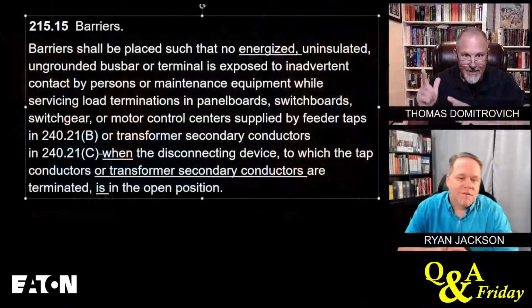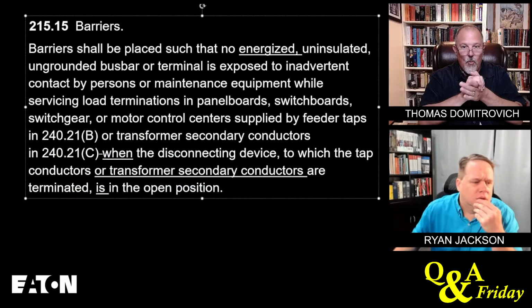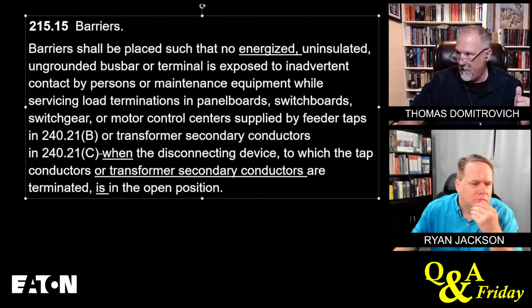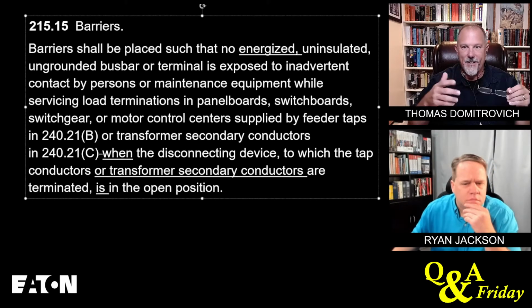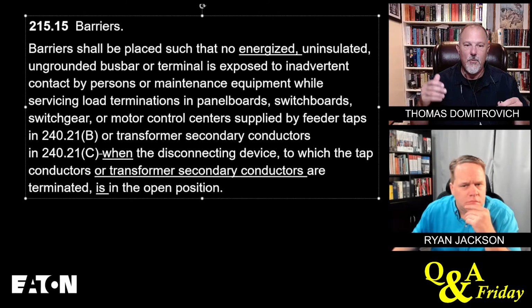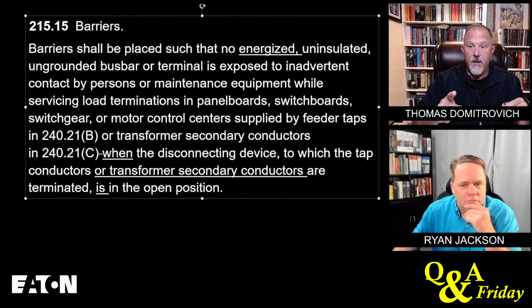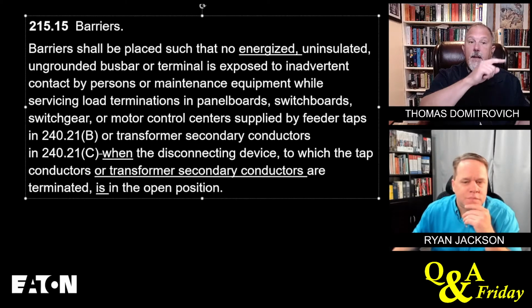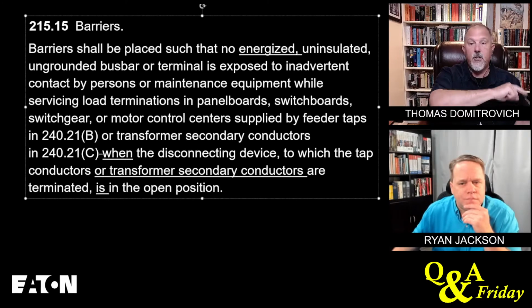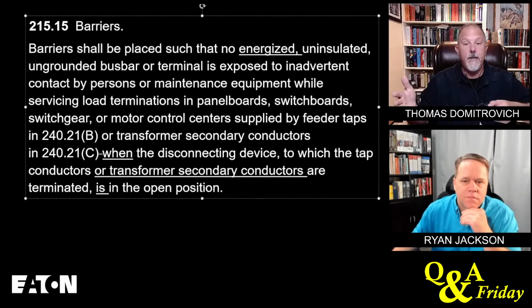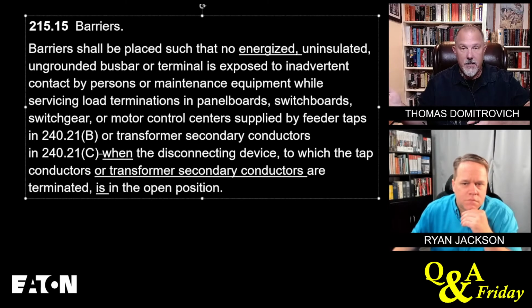Now let's go back to this. So we had this discussion when I first suggested this. I had a couple of people, more than one, let's just say, that said that all conductors on the secondary of a transformer are tap conductors, and my first reaction is, not true, because of the definition of tap conductors: if the primary overcurrent device protects the secondary conductor, then it is not a tap conductor.